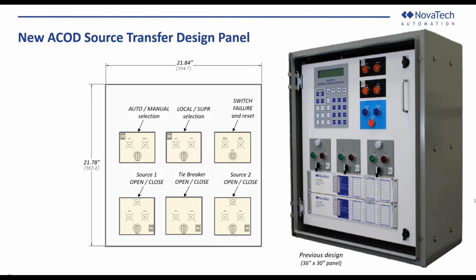And then the operator would need to disable ACOD and then correct what needs to be corrected, also switch it to local mode so that the operator can use the reset button to clear the lockout and be able to return ACOD to normal operation.